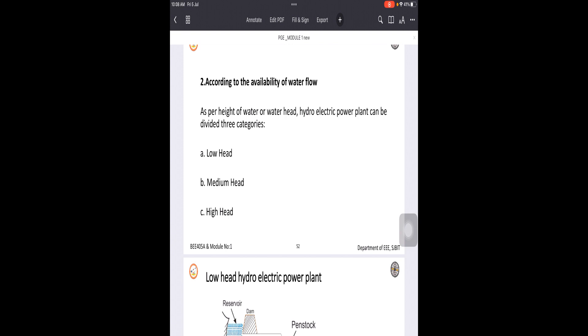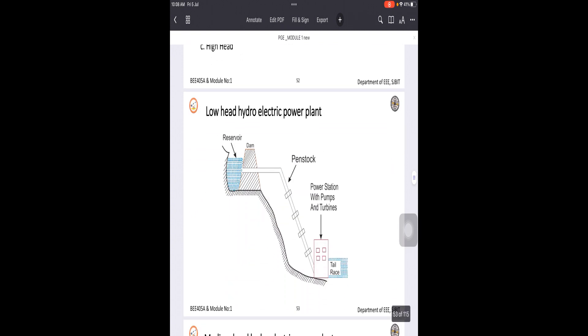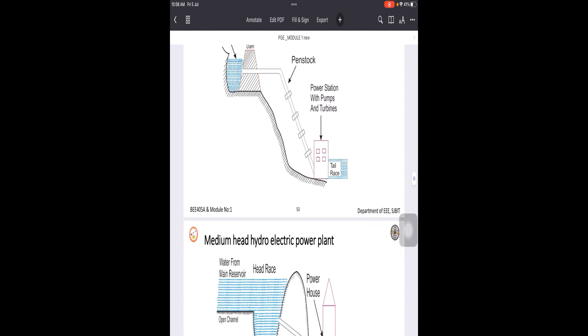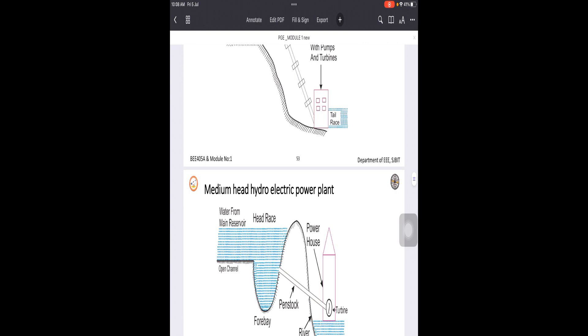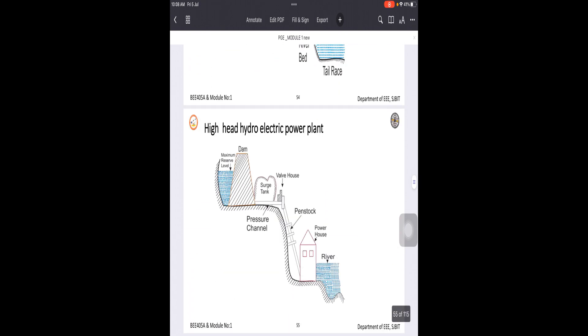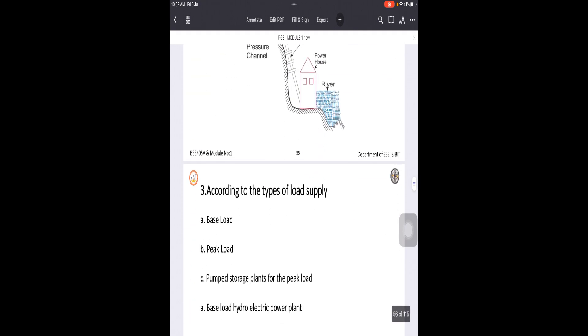Depending upon what type of power plant is suitable, these plants have been designed accordingly. If the head is less than 10 meters up to 50 meters, we call it a low head power plant. From more than 50 meters up to 200 meters, it is called a medium head power plant. More than 200 meters difference is called a high head power plant.